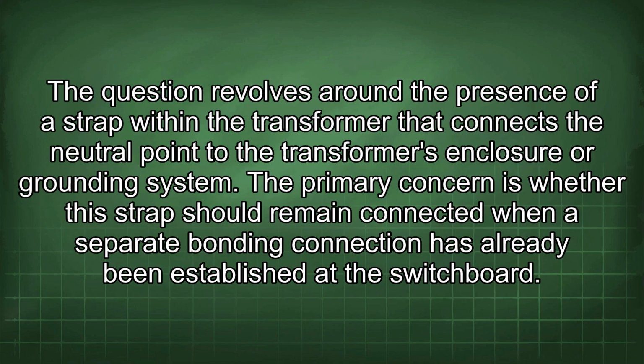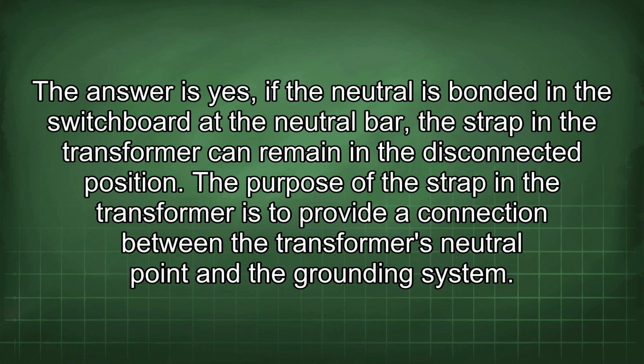The question revolves around the presence of a strap within the transformer that connects the neutral point to the transformer's enclosure or grounding system. The primary concern is whether this strap should remain connected when a separate bonding connection has already been established at the switchboard. The answer is yes. If the neutral is bonded in the switchboard at the neutral bar, the strap in the transformer can remain in the disconnected position.